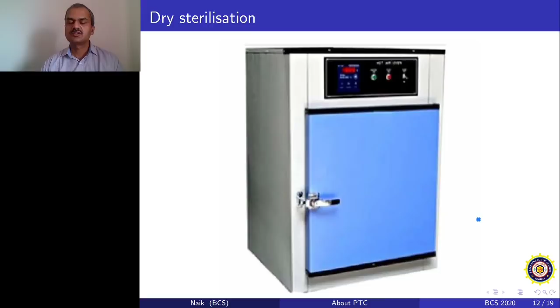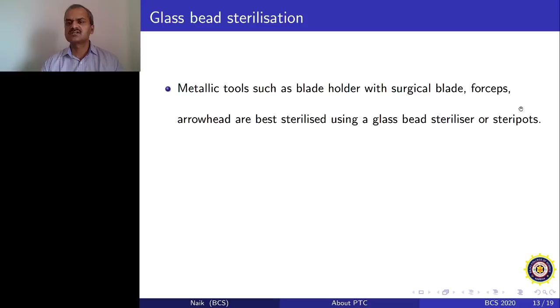Now the next one is glass bead sterilization, a technique which uses a glass bead sterilizer. It is an equipment which is basically used to sterilize metallic instruments like forceps, blade holder, arrowhead, smaller forceps, spatulas, and any kind of syringe or scissors if you have. So all metallic tools, such as blade holder, surgical blade, forceps, arrowhead, are best sterilized using a glass bead sterilizer, which is also called a steripot.